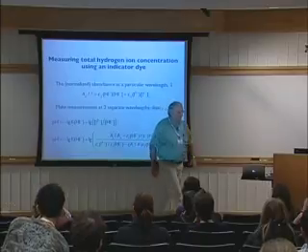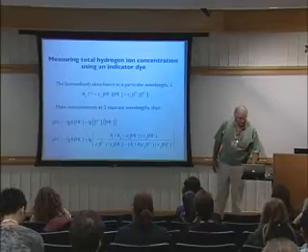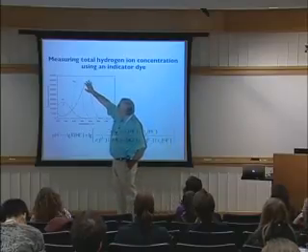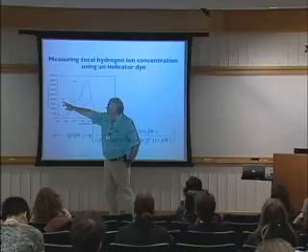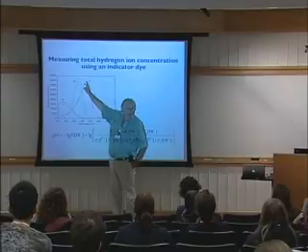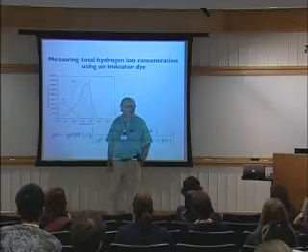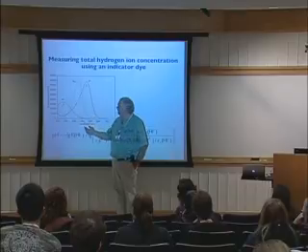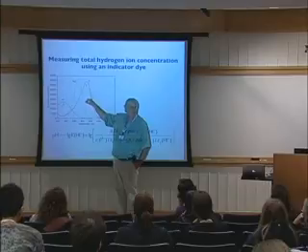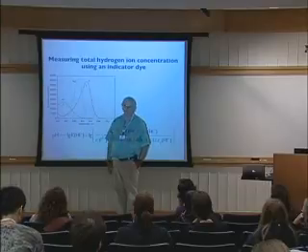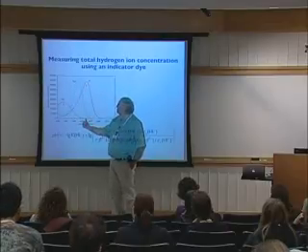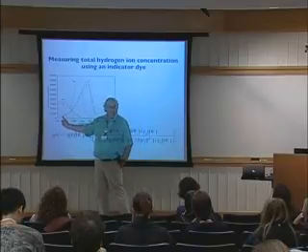The unfortunate difficulty was that we tend to do these measurements at the wavelengths corresponding to the peaks. Why? Because if your system doesn't measure the wavelength very well, you don't actually get much error added by that. You could, in principle, take any two wavelengths, but it would be verging on careless to do one halfway down the peak, because the slightest problem with the wavelength, you've got a big change in the extinction coefficient. So it's usually on the peak, but under this peak, there's a tiny bit of this species. And under this peak, there's a meaningful amount of that species.